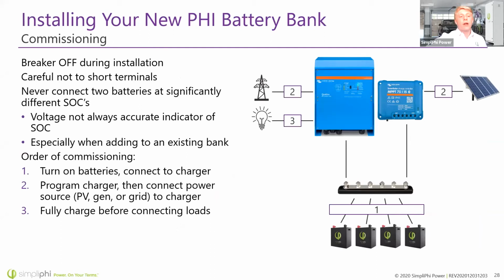Now, commissioning. Once you've got all that wiring done, make sure to keep the breaker off during the wiring and then follow this order of commissioning. Once you've verified that all the voltages are within a volt of each other, everything is wired in parallel, and none of them are wired reverse polarity, go ahead and connect them to the bus bars and turn on the breaker on each battery. That's going to connect you to, let's say, the charge controller. Then connect the charge controller to the power source like the PV panels. Turn that PV disconnect to the on position and allow the batteries to charge fully before powering loads. Loads are going to be connected last. You can keep your loads breaker in the off position during the install, and once you're finished charging the batteries, you can turn the loads breaker on.